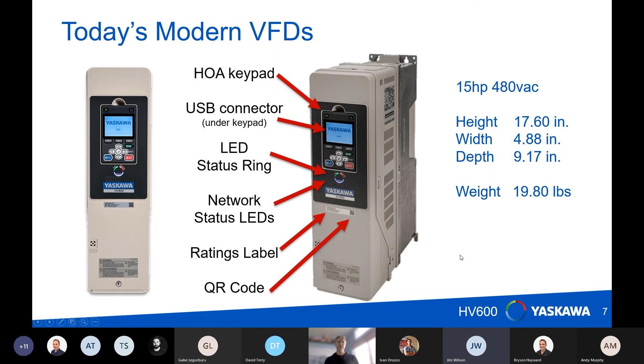This new keypad has a menu-driven startup. Even though we still ship a user manual, you don't need that manual to start this drive. You go to the application you're using, and it asks you questions to answer to get the drive up and running. You can customize the screen with up to a dozen different parameters, or use bar graphs, analog gauges, or trend a parameter on that display if you want.